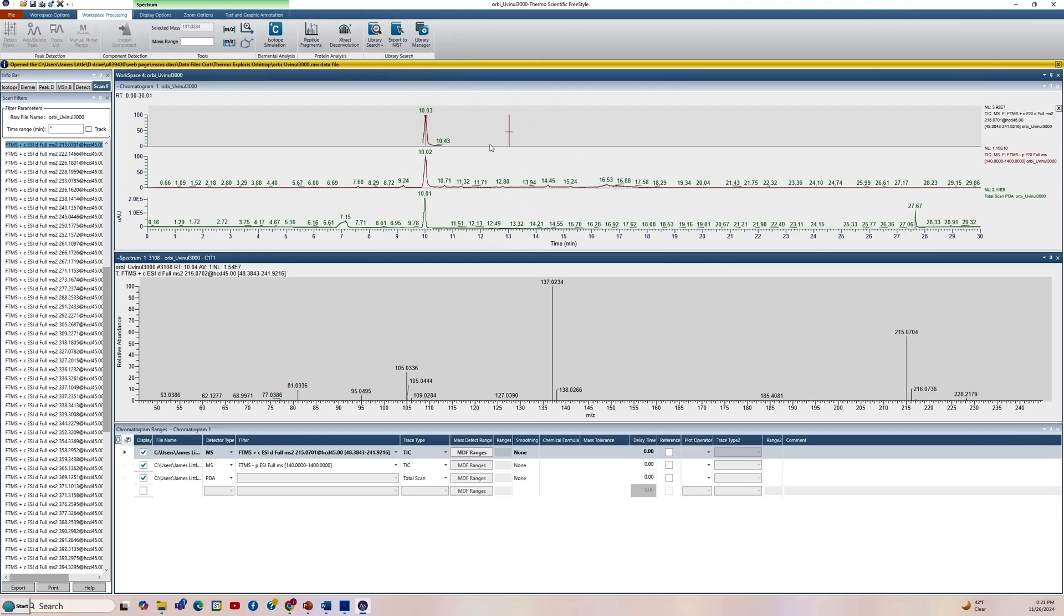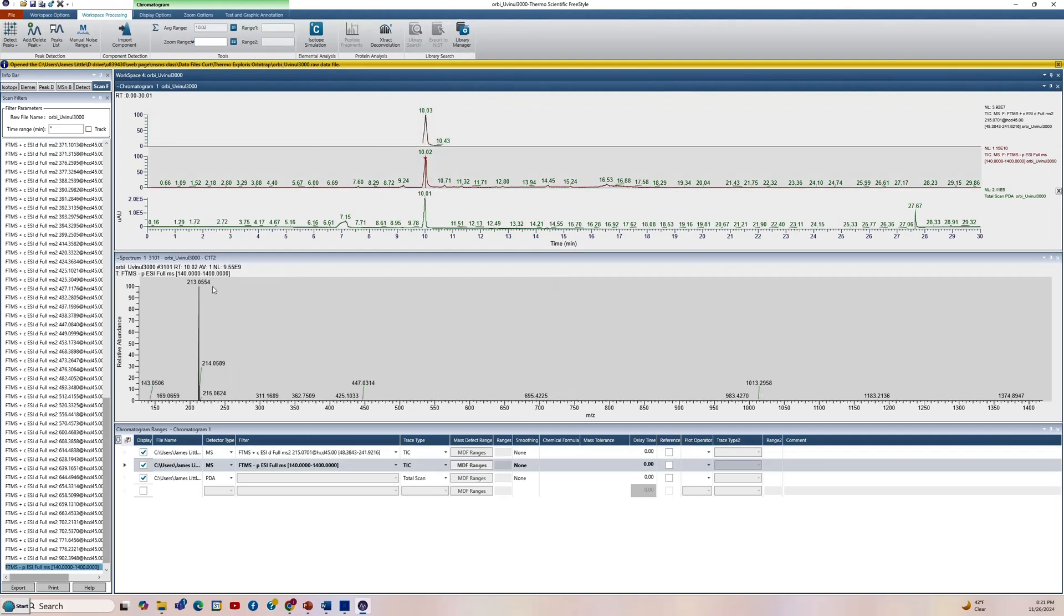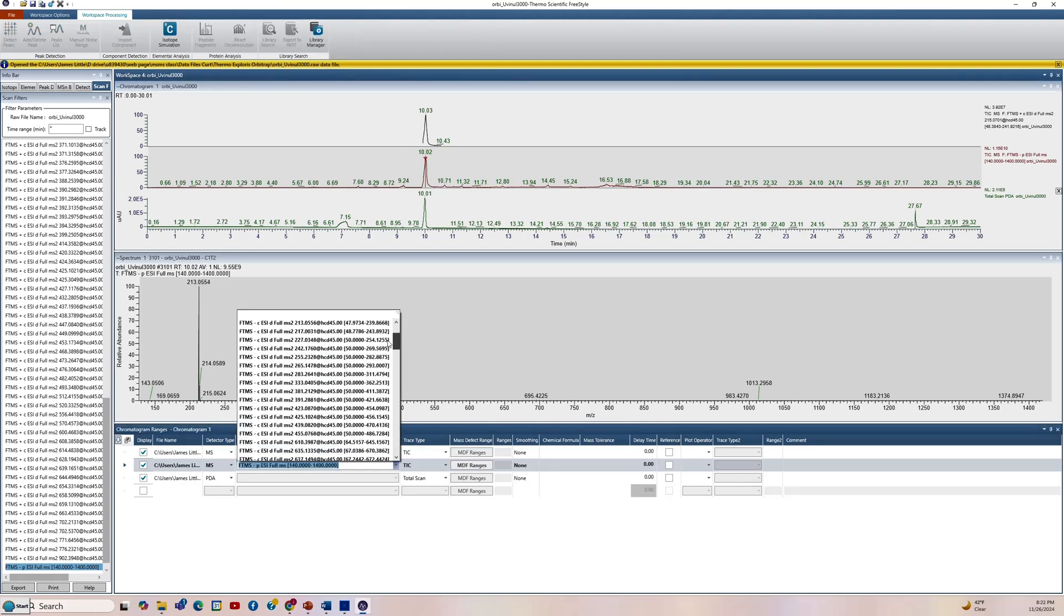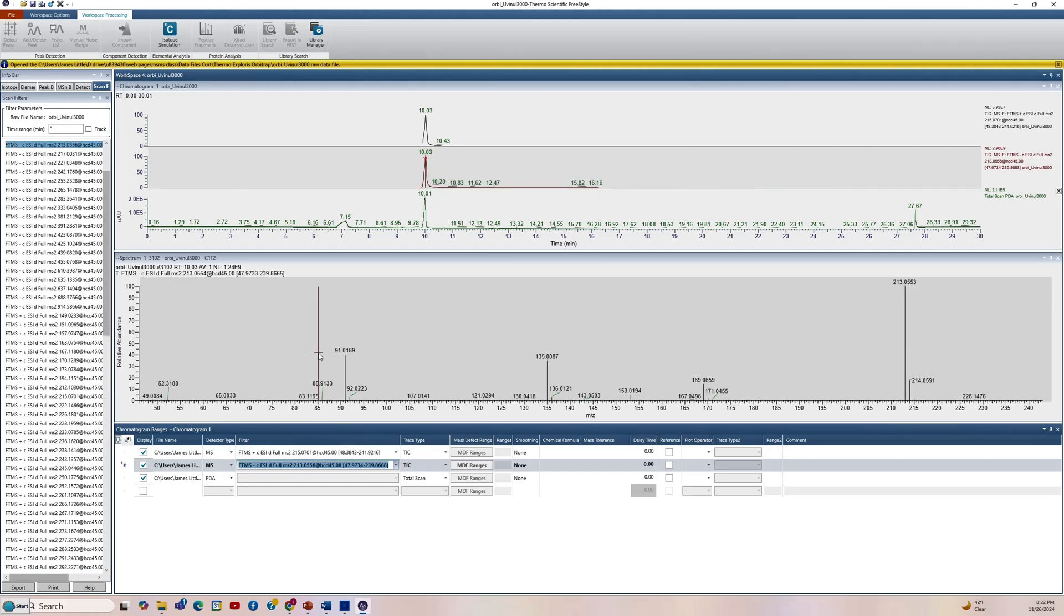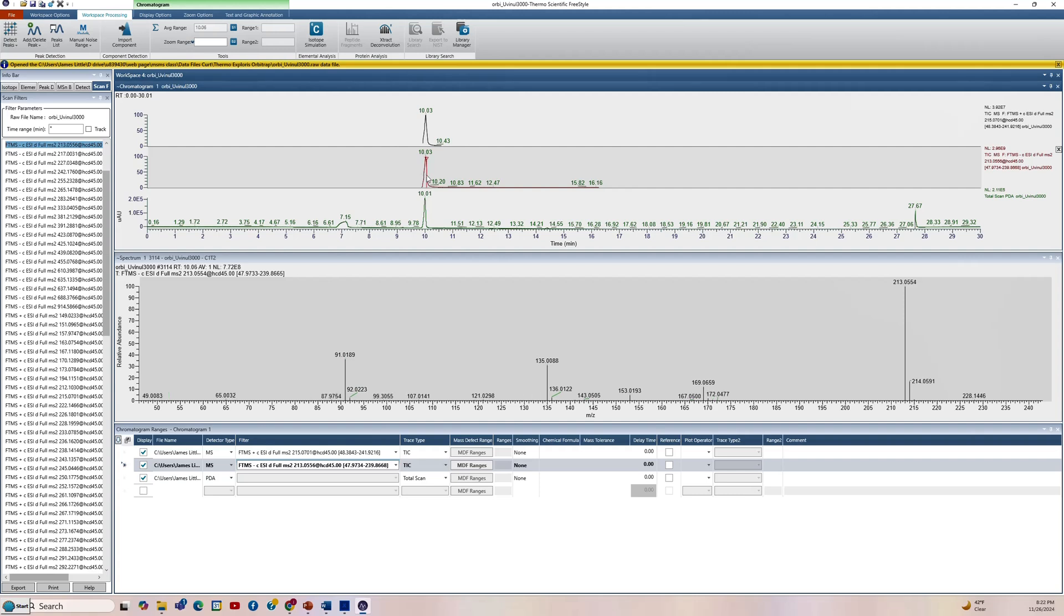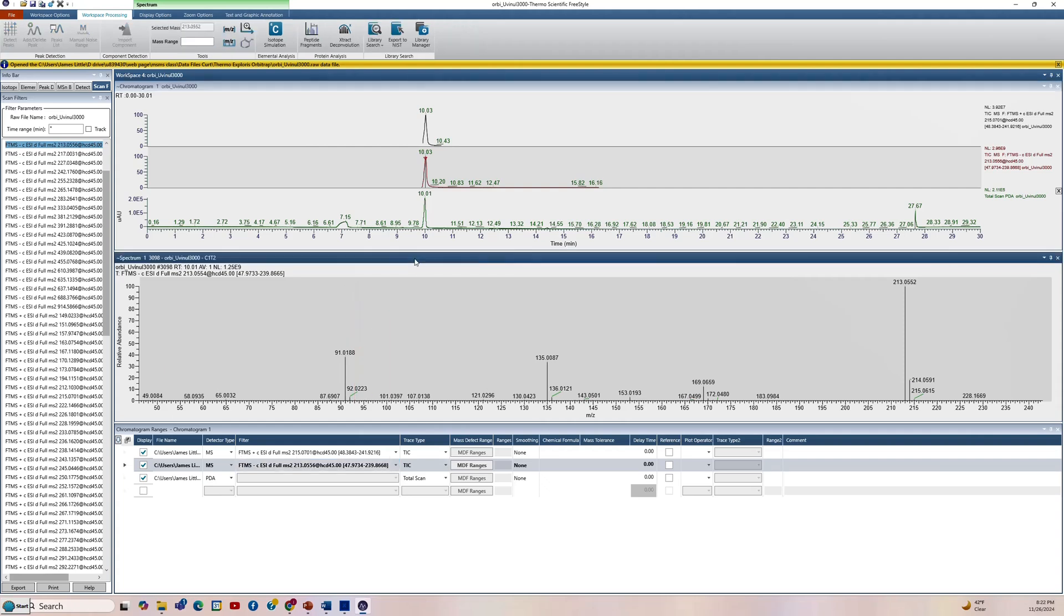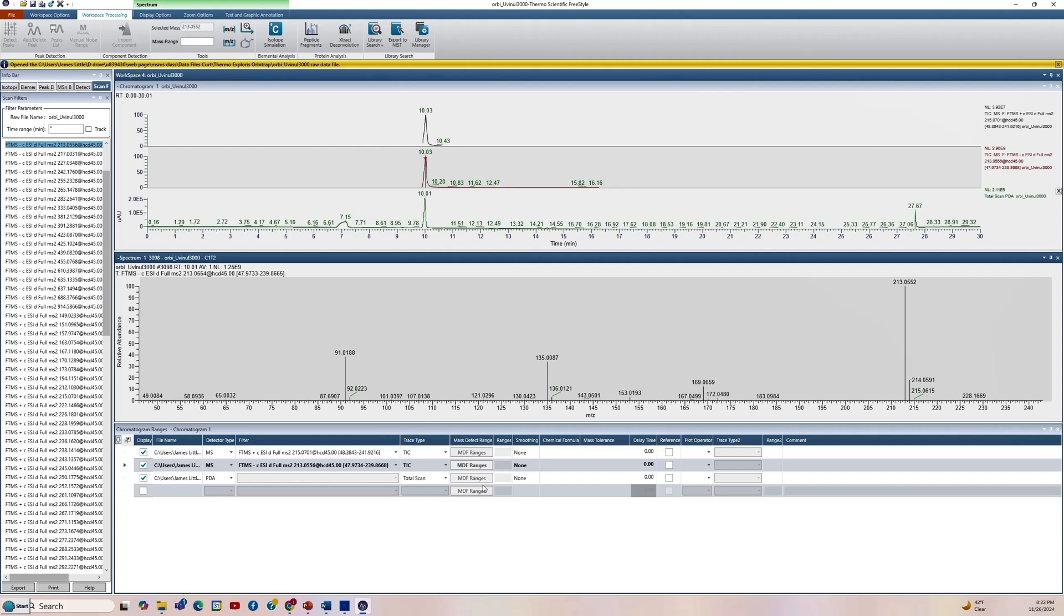The same thing for the negative ion here. If we click on it, we'll see we need the 213. Come down to the filter. We'll go until we find the negative ion trace. So we're looking at the negative ions here. We're looking for 213. If we single left click on it, you can click several different places if you want to see if it's consistent through it, but it looks like it is. So I'll just click at the top where it's the most intense. We've got a nice M minus H ion and then the fragment ions. We could left click this and export to NIST for searching. So that's pretty much how you get things ready to send to the NIST search from MS-MS data.